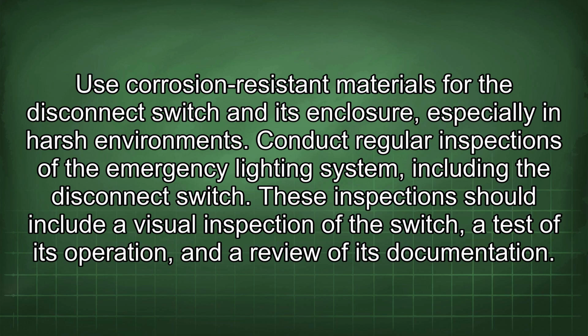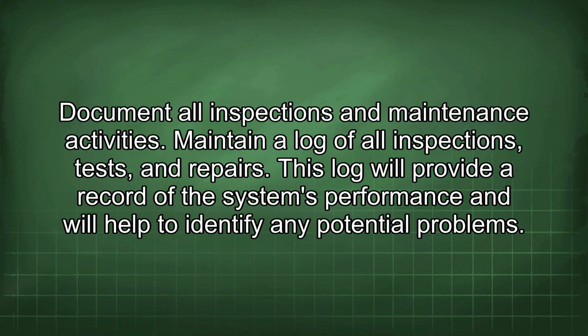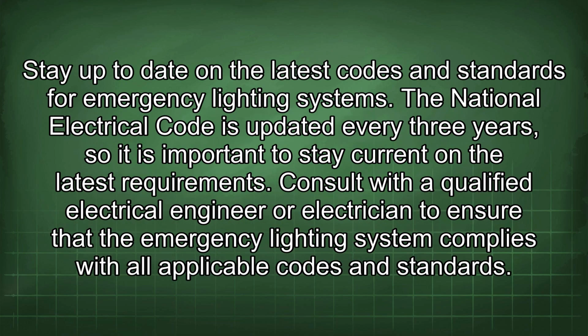Conduct regular inspections of the emergency lighting system, including the disconnect switch. These inspections should include a visual inspection of the switch, a test of its operation, and a review of its documentation. Document all inspections and maintenance activities. Maintain a log of all inspections, tests, and repairs. This log will provide a record of the system's performance and will help to identify any potential problems. Stay up to date on the latest codes and standards for emergency lighting systems. The National Electrical Code is updated every 3 years, so it is important to stay current on the latest requirements. Consult with a qualified electrical engineer or electrician to ensure that the emergency lighting system complies with all applicable codes and standards.